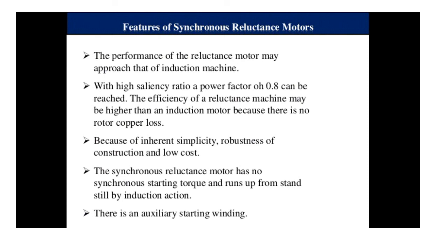Because of inherent simplicity, robustness of construction and low cost. The synchronous reluctance motor has no synchronous starting torque and runs up from standstill by induction action. There is an auxiliary starting winding.